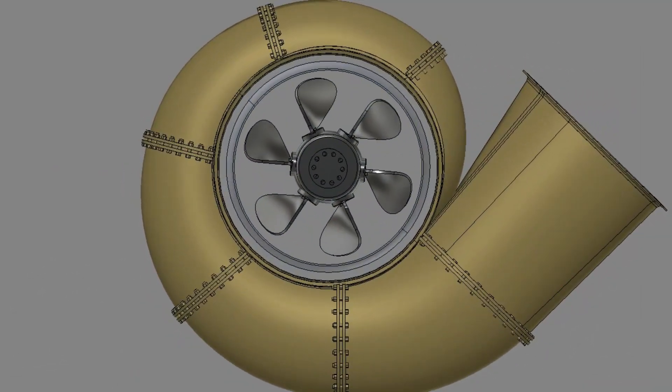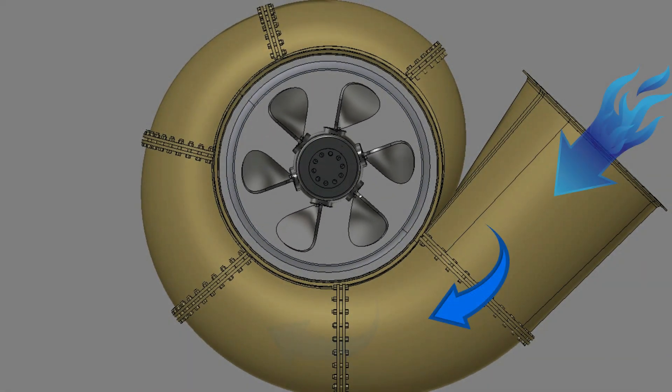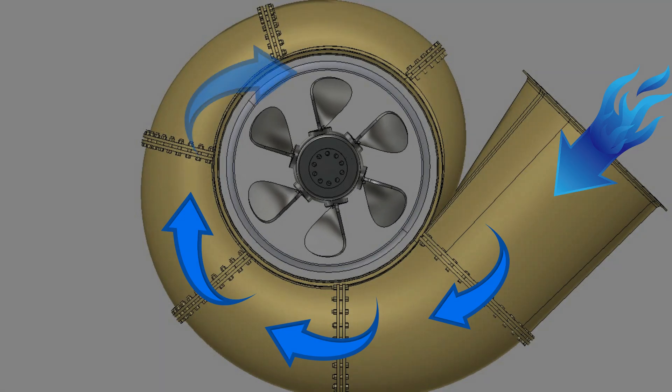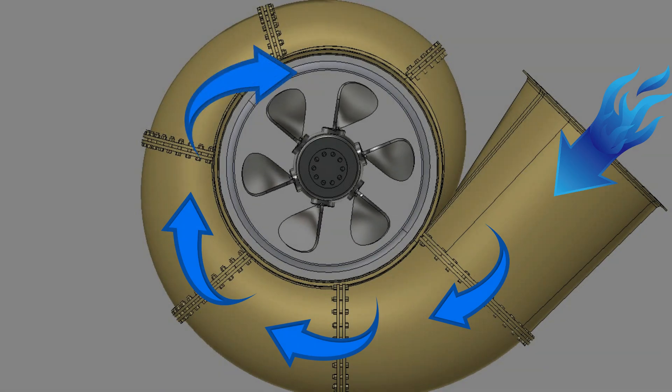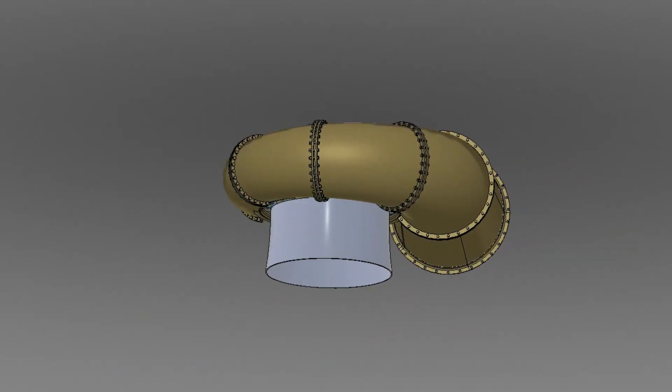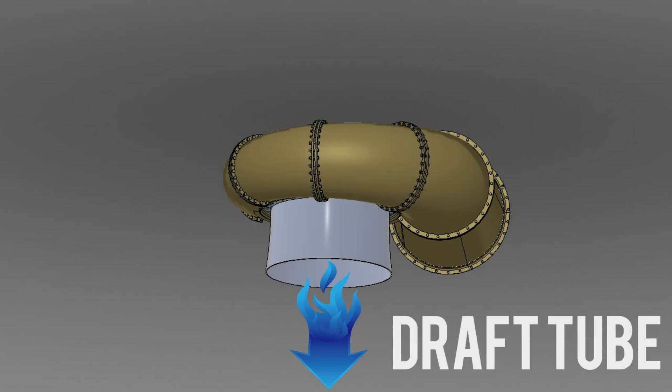Water from the head race enters the scroll casing and then moves to the guide vanes. From the guide vanes water turns through 90 degrees and flows axially through the runner. After passing through the runner, the water is discharged to the tail race through a gradually expanding tube called the draft tube.